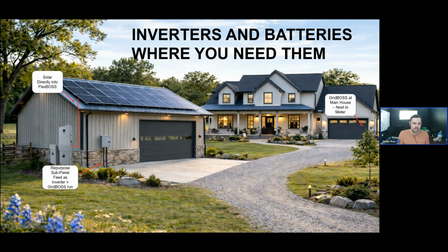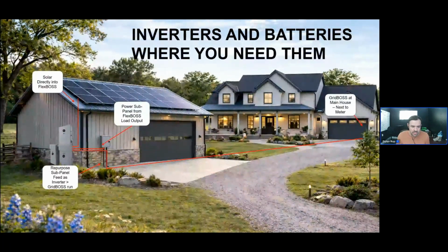As we said, solar goes directly into the FlexBOSS. And then what's really cool about this solution is we can actually repurpose the sub panel run, and use that run now, instead of going from the distribution panel of the home, to go into the inverter and over to the GridBOSS. You're not having to pull a whole new circuit. You might have to just add a junction box and extend that circuit a bit, but it gives you the ability to deploy this system at a separate location, repurpose some of the existing infrastructure without having to trench or dig a new line, and have a really easy mechanism to make that AC connection back to the GridBOSS from the inverter. And then we can simply have a second output from the inverter that goes directly to power that sub panel on site. So we still have essentially delivered the promise of whole home backup.